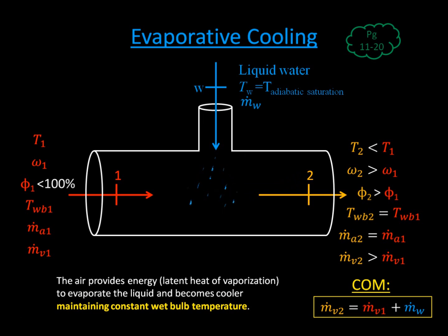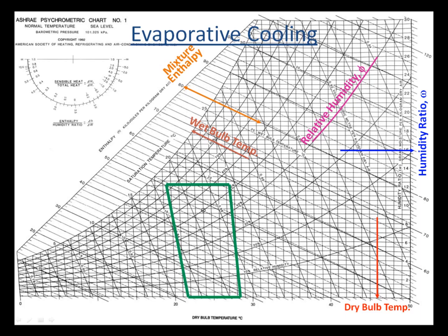My relative humidity is going to increase because my bucket carrying capacity has decreased, right? And I've also increased the vapor as well. That's also going to increase the relative humidity. So my bucket size is shrinking, but I'm also adding vapor, and I can do that all the way until I'm 100% saturated. And here's the key detail: my wet bulb temperature remains constant. That's important when you're using your psychrometric diagram. So let's look at the psychrometric diagram.